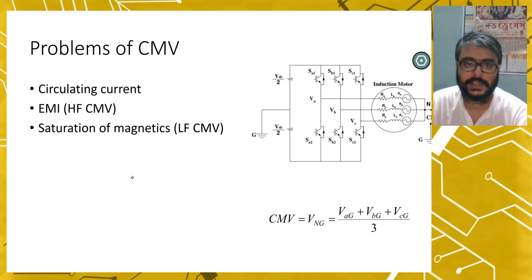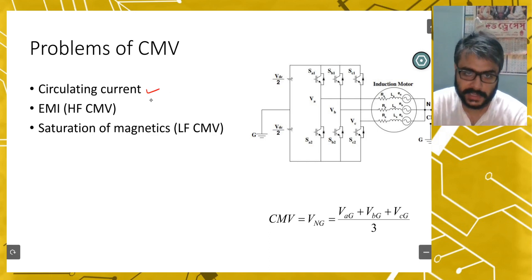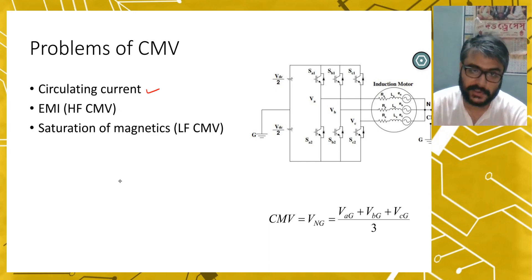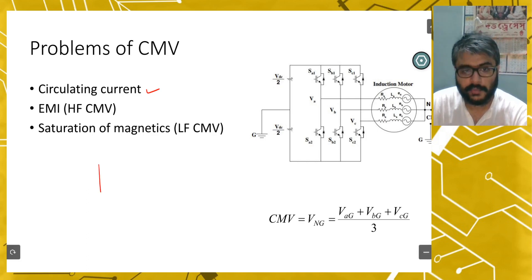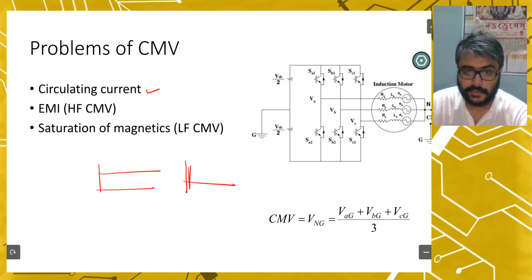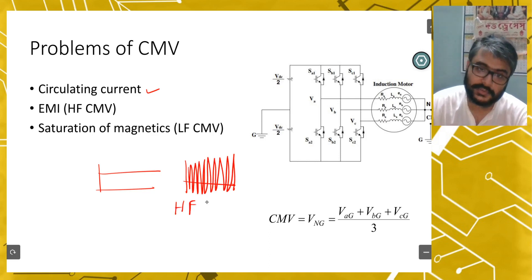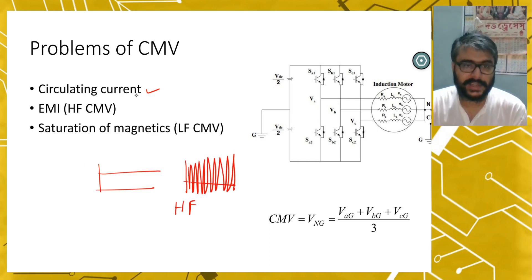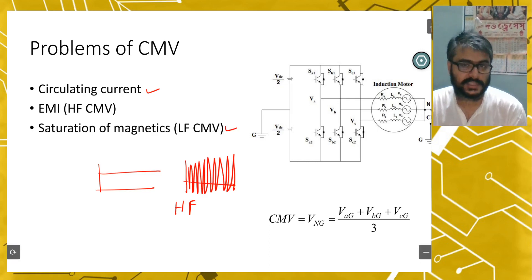What are the problems of common mode voltage? An important, actually very important problem is circulating current, which we will talk about later. And electromagnetic interference — this is due to high-frequency common mode voltage. When there are very high-frequency oscillations in common mode voltage, this will create issues. This circulating current may also create issues like saturation of magnetics.